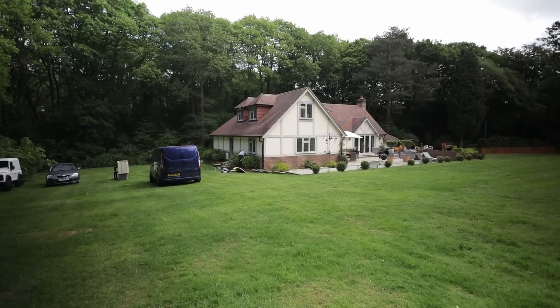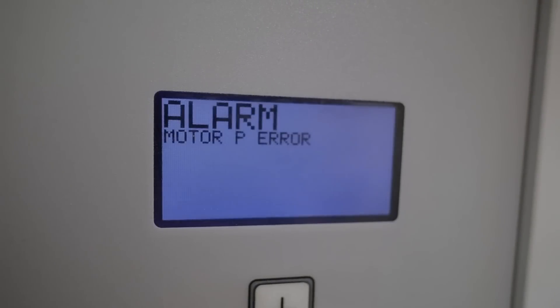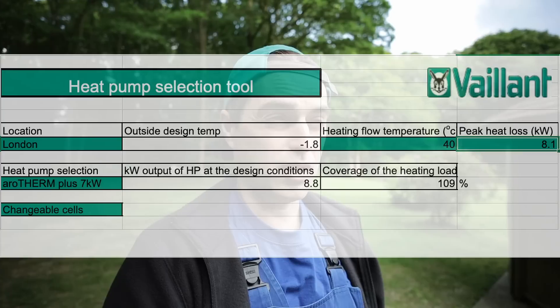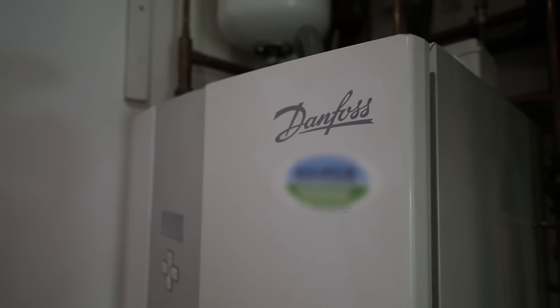We are literally in the middle of nowhere. The house we are working at is 170 square meters, a new build. The existing heat pump lasted 13 years — it was made by Danfoss. Unfortunately spare parts are no longer available and this model is no longer manufactured, so there's no other option than to replace it. We will be installing a 7 kW Aerotherm Plus. Why 7 kW? Because 7 kW is rated at minus 7°C, so at our design temperature of minus 1.8°C that unit at a flow temperature of 40°C will give us almost 9 kW.